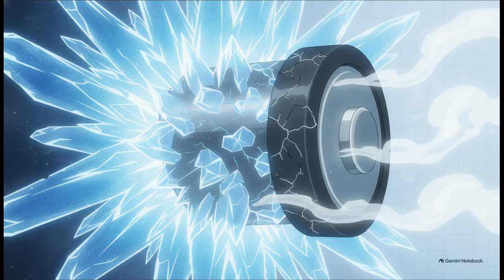The physical failure mechanisms at sub-zero temperatures are massive threats to structural integrity. Organic electrolytes experience severe thickness surges, and physical components begin to freeze and snap. Below -20 degrees Celsius, the fluorinated rubber seals completely lose their elasticity, causing microcracks, and at -15 degrees, the aluminum current collectors become about as brittle as dry pasta. That dramatically heightens the risk of an internal short circuit.